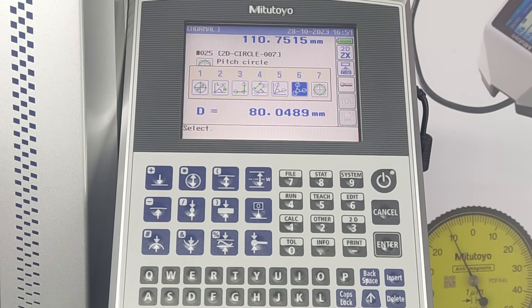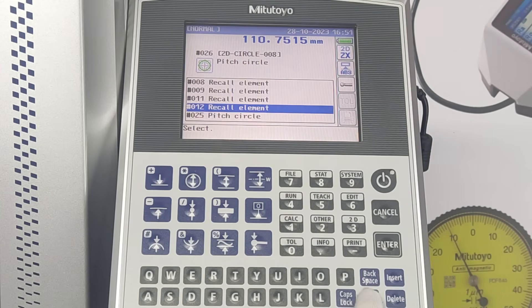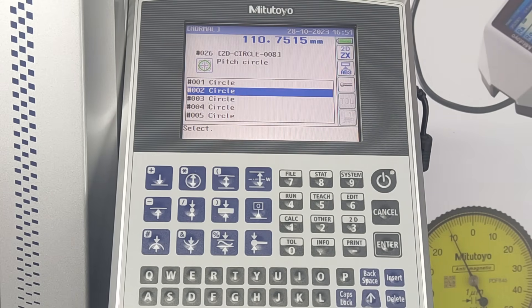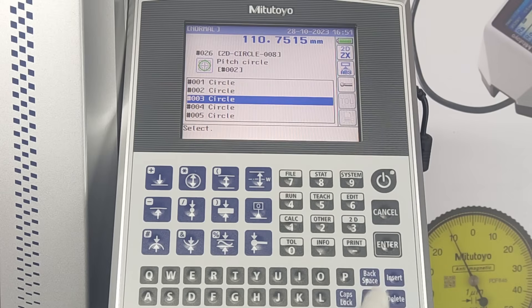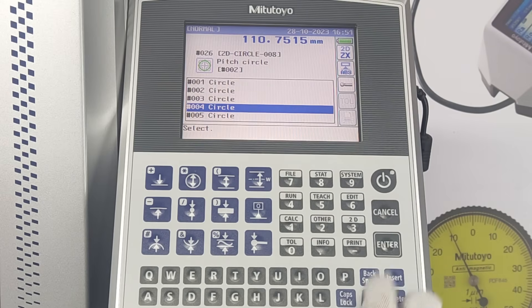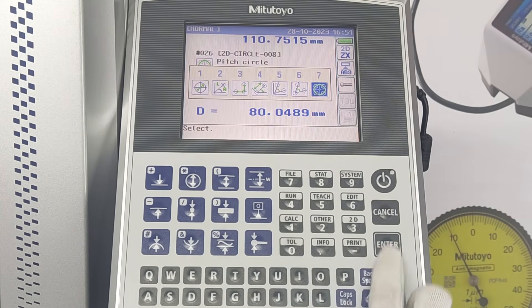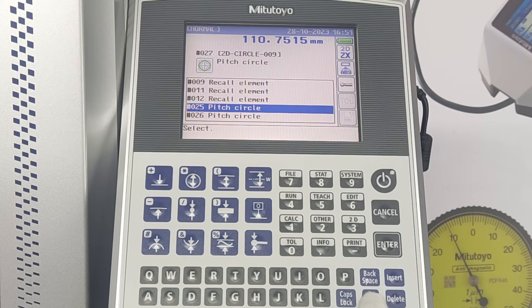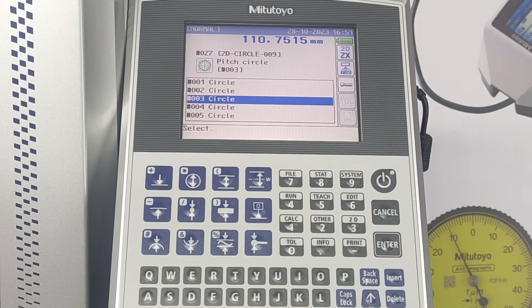The seventh option is pitch circle. In this option, three or more circles are to be selected to determine the center X, Z coordinates and diameter of the pitch circle. Correct result will not be obtained if the selected circles are not used in pitch circle.